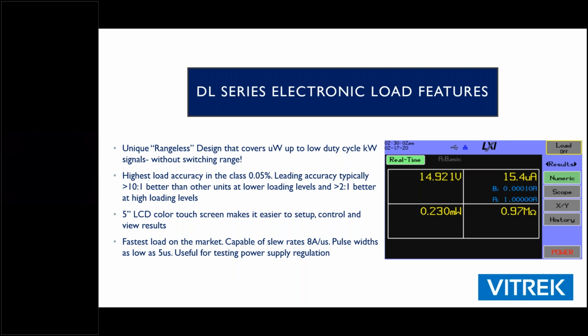Some of the features - I think one of the biggest ones is that we're rangeless. So there are no periods where we're not able to load or give you a measurement result because we're switching ranges and missing a small portion of data. Our accuracy is something we not only specify, but actually hold ourselves to. Some of the other loads out there you'll find are specified very generally, and we were able to do some head-to-head comparisons and find situations where people are not necessarily complying with their specs. We've definitely tried to specify our product very realistically and stay within those specs.